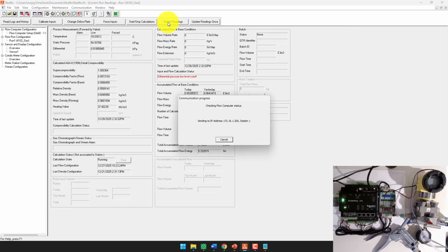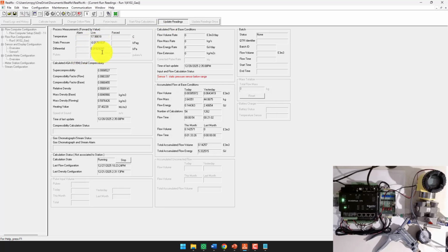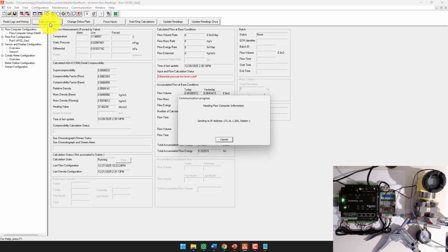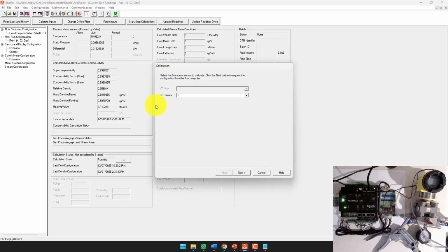And now if we hit update readings, you'll notice this 54 will be closer to 0. So now we're sitting at 0 for the static pressure. We'll do the same process for the differential pressure. Go calibrate inputs. Pick the sensor that we want. We only have one sensor. Hit next.